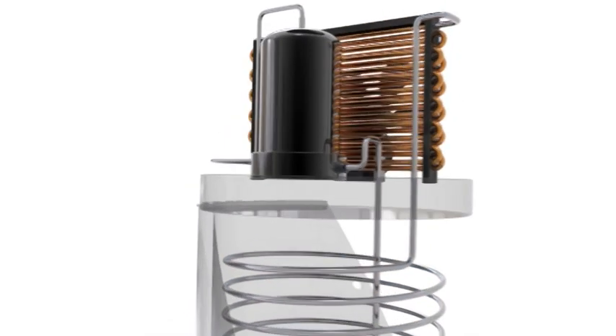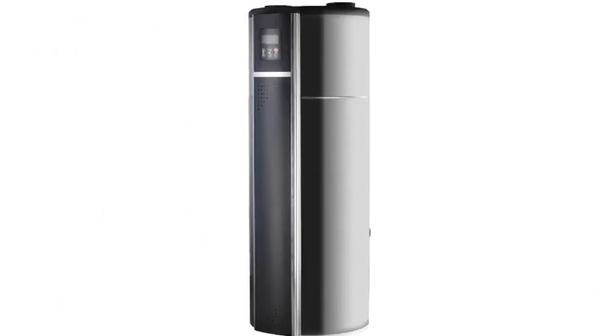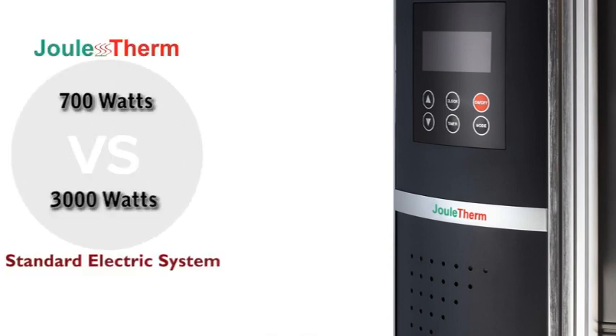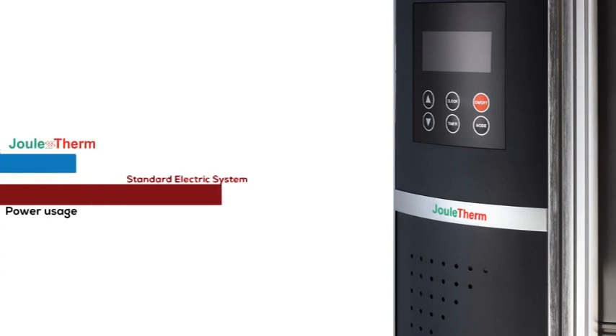This process continues until all the water stored in the tank is heated to a full 60 degrees. The advantage of the heat pump is that it requires only 700 watts of power versus the 3000 watts used by electric elements. This allows the JouleTherm to provide the same amount of hot water as an electric water heater, but using just one quarter of the power.